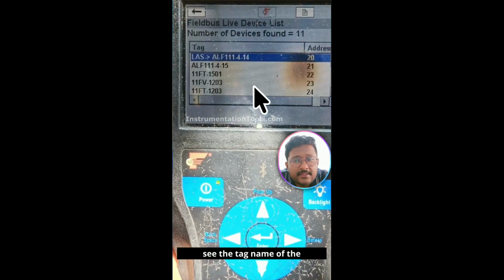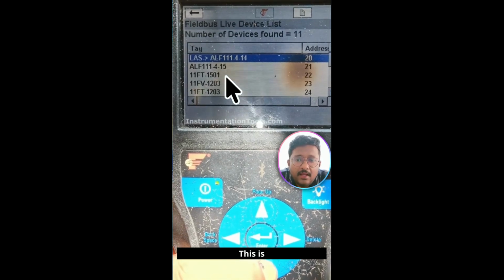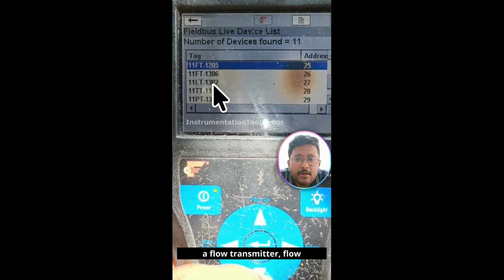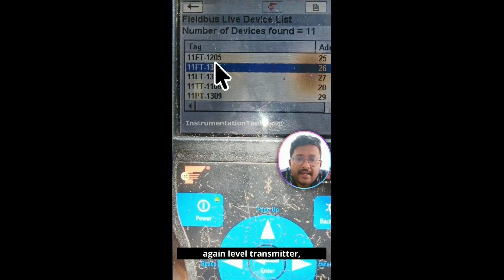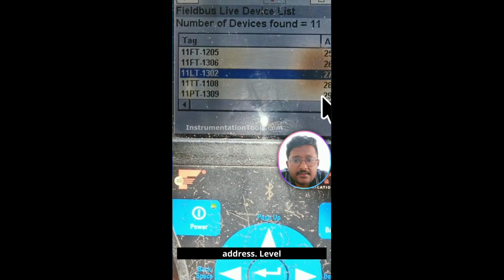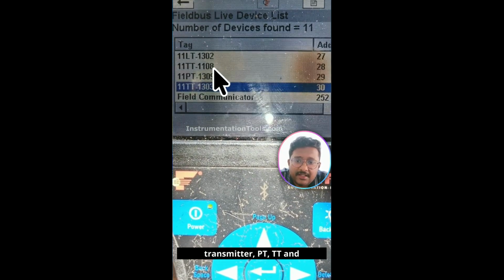And now we are seeing the live list. Now I will show you all the instruments connected to this network, and you can see the tag name of the instrument and the device address. Okay, this is a flow transmitter, flow valve, flow transmitter again, level transmitter, temperature transmitter, pressure transmitter. And you can see the device address also, the node address or device address. So level transmitter, temperature transmitter, PT, TT, and then field communicator.